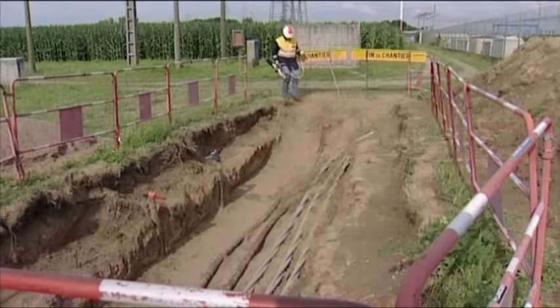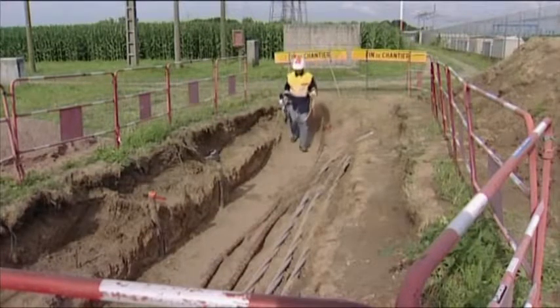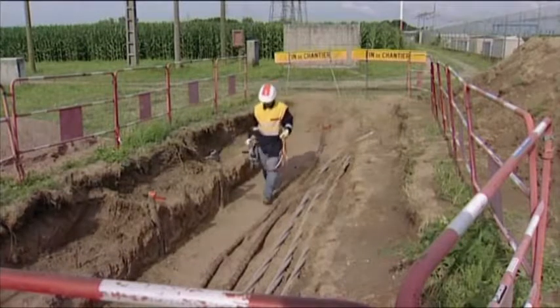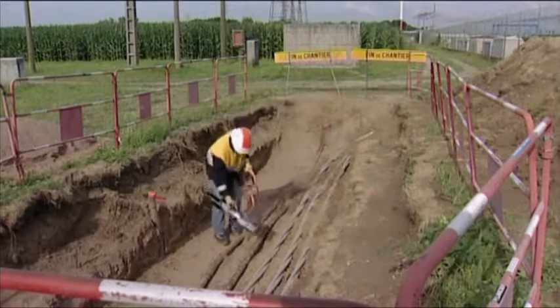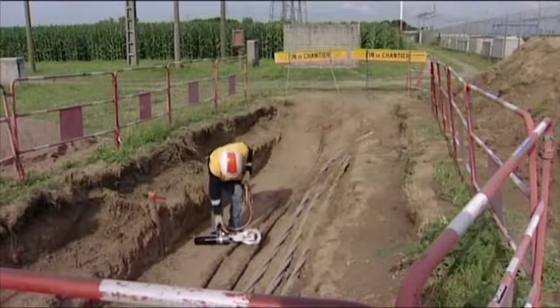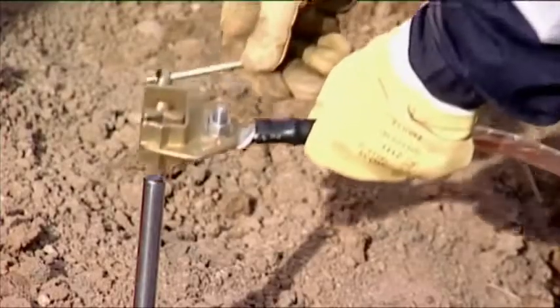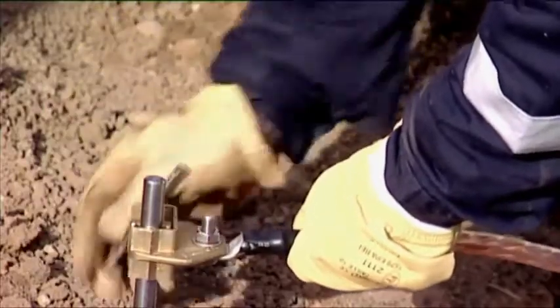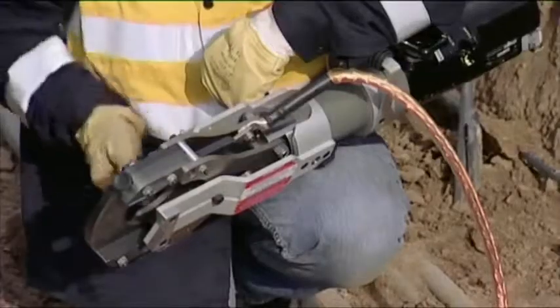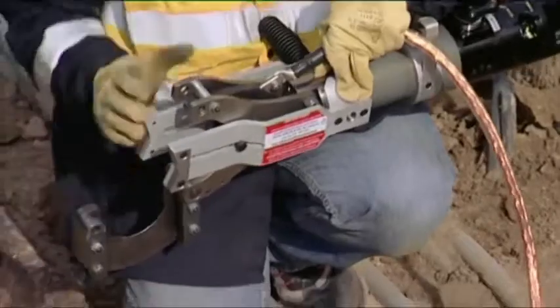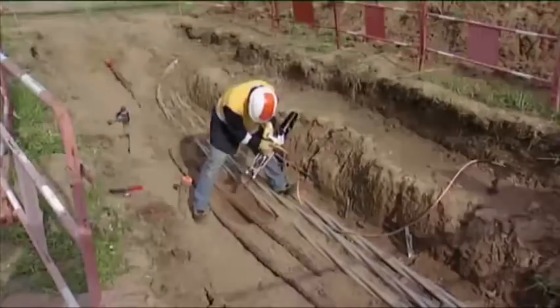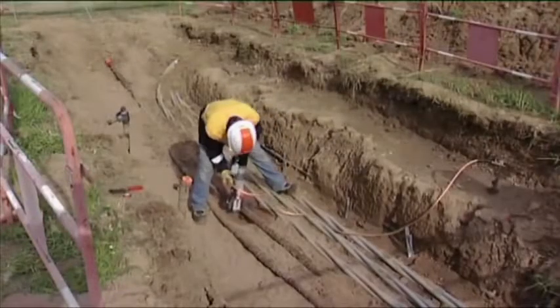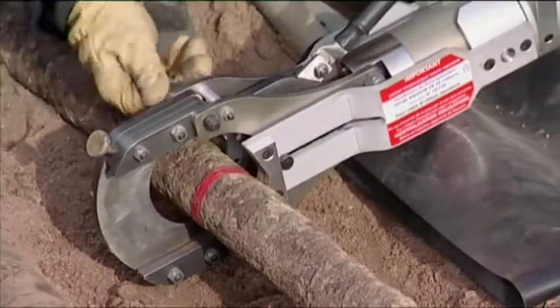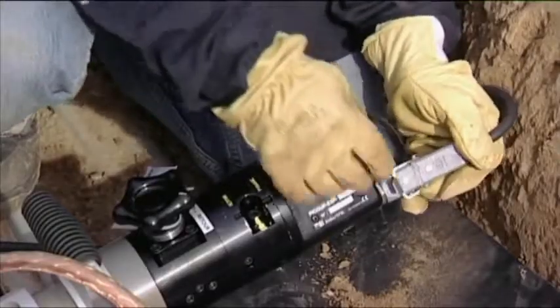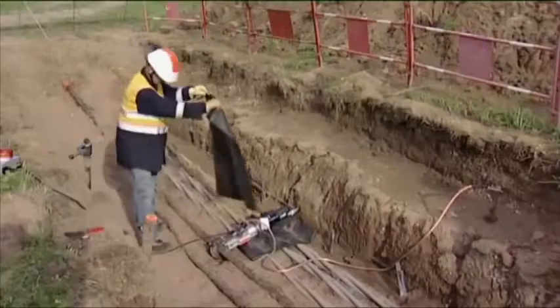The P-coupe is an autonomous hydraulic device. When using this device, you link the clamping action for the cable spiking operation with the complete cutting of the cable. The P-coupe offers two additional safety features in the event there's still voltage in the cable. Firstly, it is grounded to evacuate any remaining power into the ground and enable safety features to function. Its operating speed is calibrated to be certain of providing unipolar fault, and also it is designed to ensure the complete safety functioning sequence.